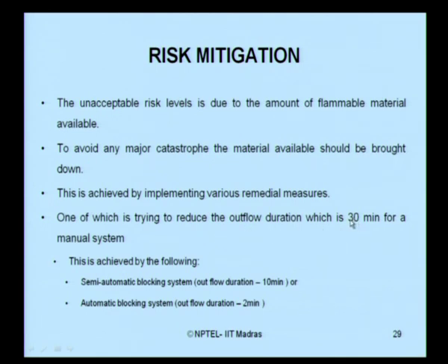So, there is an extensive delay in controlling that particular mitigation. If I use a semi automatic, I can control the disaster in 10 minutes. If it is an automatic, I can use the control mechanism in less than 2 minutes. Remember that whatever control mechanism you have in a system, you have got to give a weightage in analysis for what we call as the blocking system.